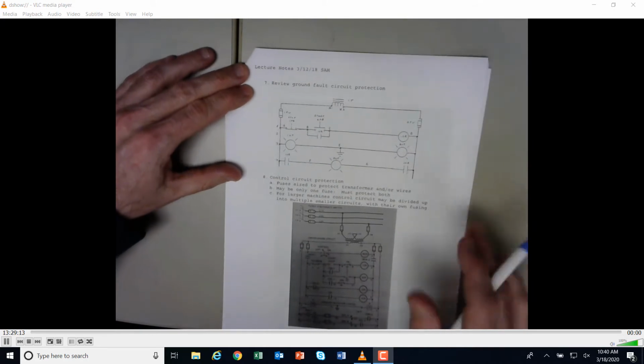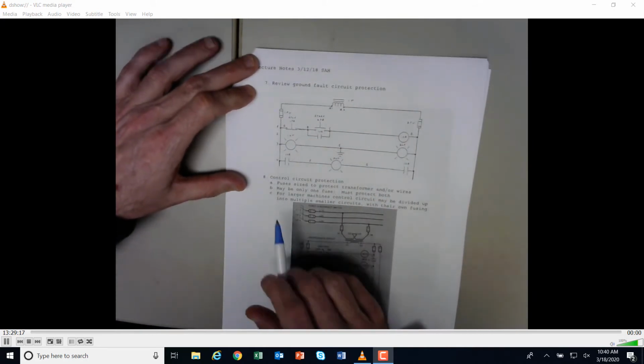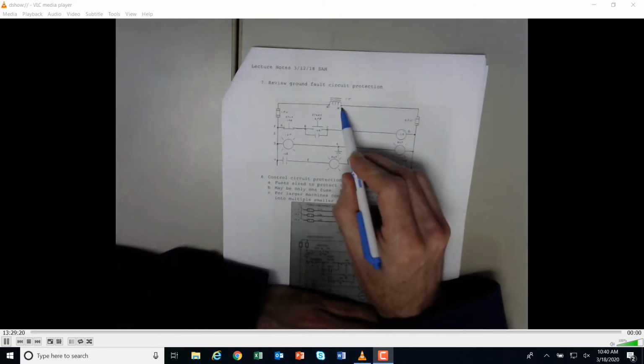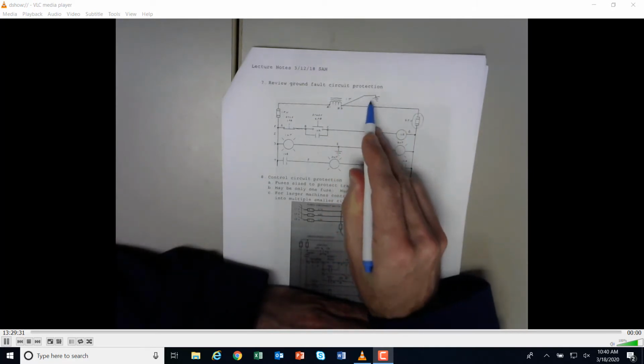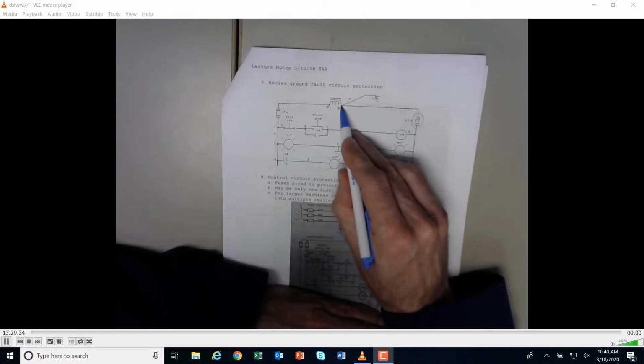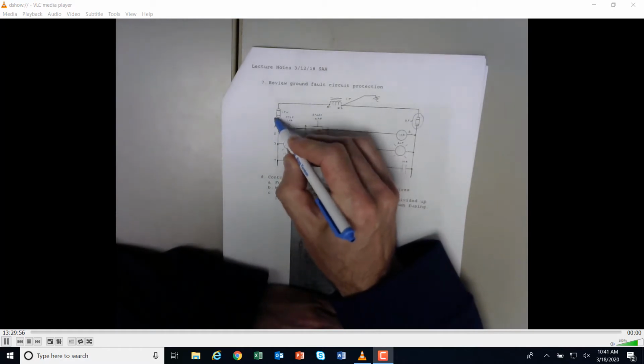Okay. Now when we take a look at the ground detect circuit, that's what you're going to be analyzing right here. So this has an ungrounded secondary. A grounded secondary would have a ground right here, and then we wouldn't need this fuse, but ours is not grounded. So what does that mean? Well, if this had a ground to it, then if there was any kind of a short or a fault on here, each side of the load is run directly to earth, which means that if you had a short circuit on any one of these things, this fuse is going to blow because there's going to be current flow to earth.